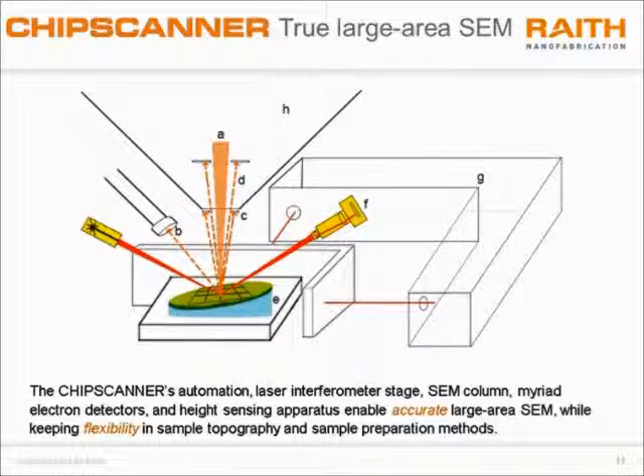We also have, the chip scanner has a state-of-the-art scanning electron microscope column, and the primary beam can be varied in energy, just like any traditional scanning electron microscope. Also, myriad electron detectors like the Everhart-Thornley detector, the post-lens angular selective backscatter detector, and also in-lens secondary and backscatter electron detectors are all possible with the chip scanner. Finally, we have height sensing apparatus. So when you are imaging over large areas, it is important to keep the sample in focus. And this is a common problem for electron beam lithography. So that's why the chip scanner has built-in laser height sensing apparatus. And this allows the chip scanner to keep the sample in focus over large areas.